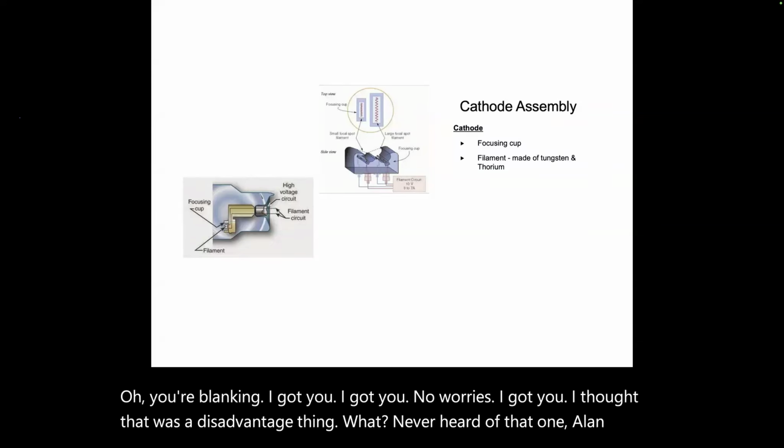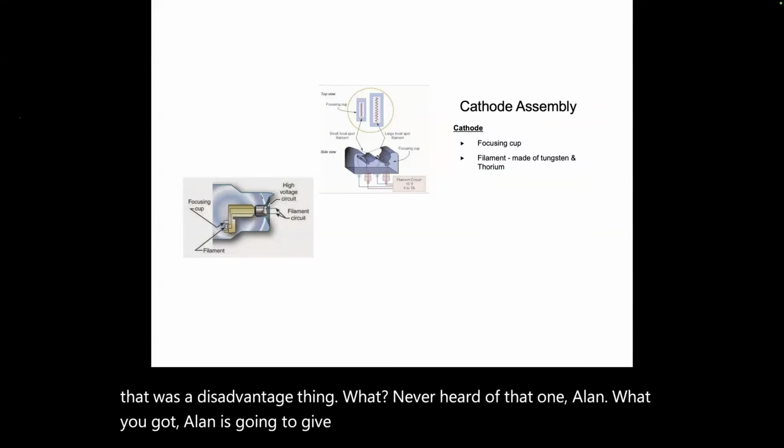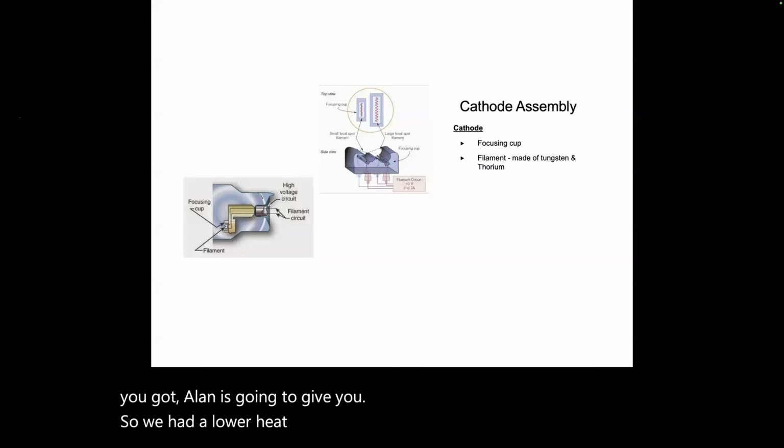Alan, what you got for me? The disadvantage for the small focus filament is that it doesn't dissipate heat as much as the large. Yeah, so we have a lower heat capacity. I mean, you have to use a lower mA setting. Phoebe, question or comment?